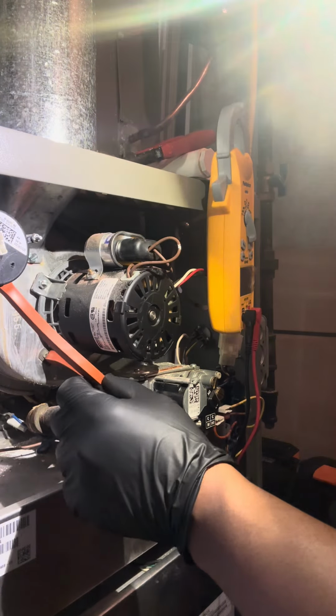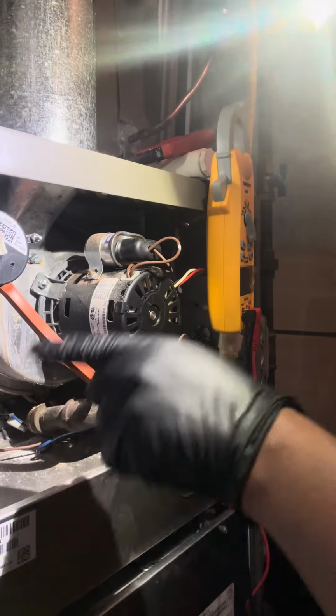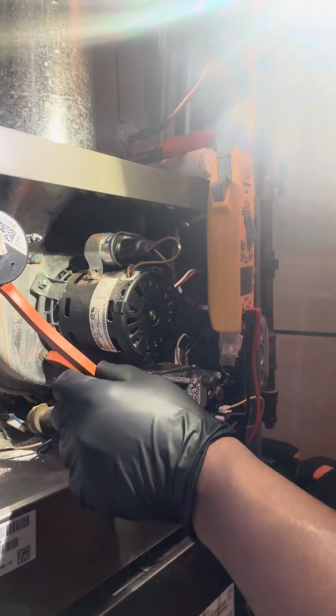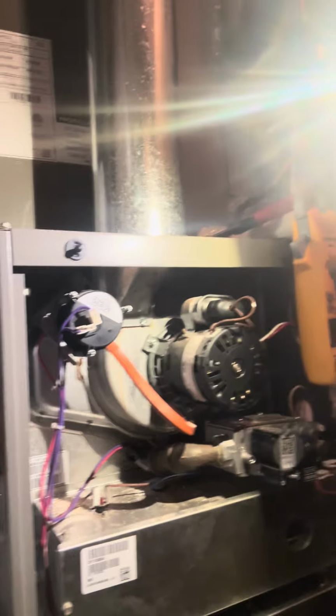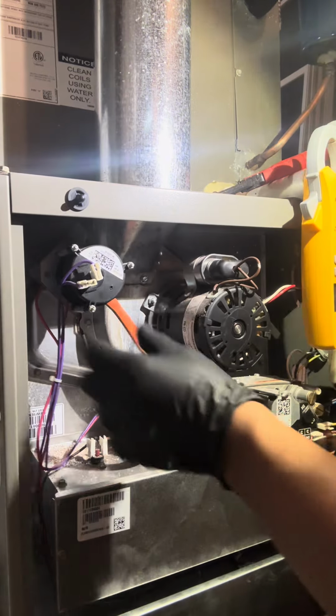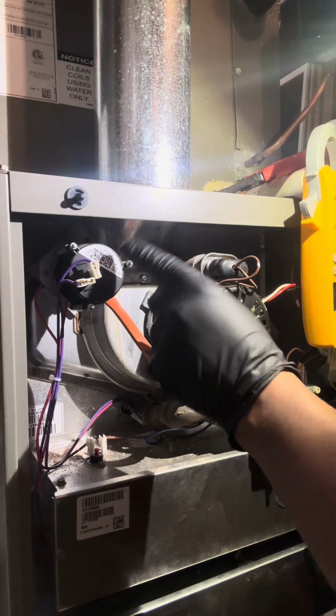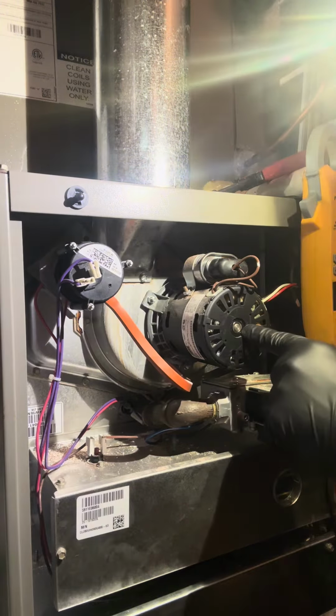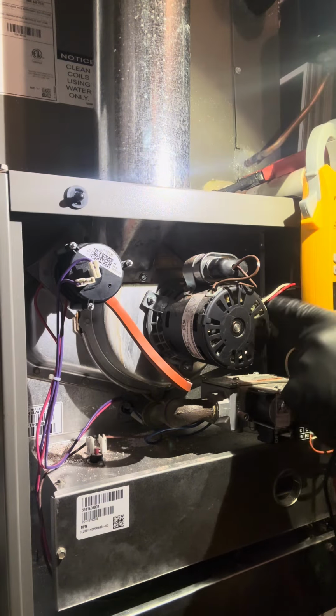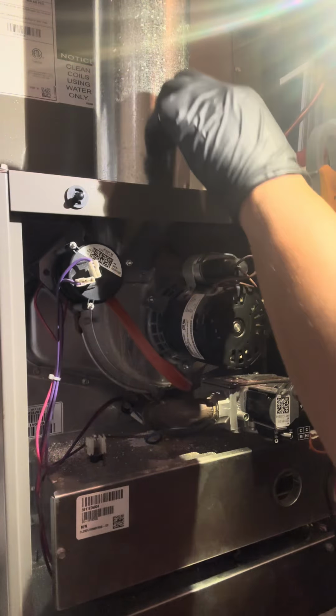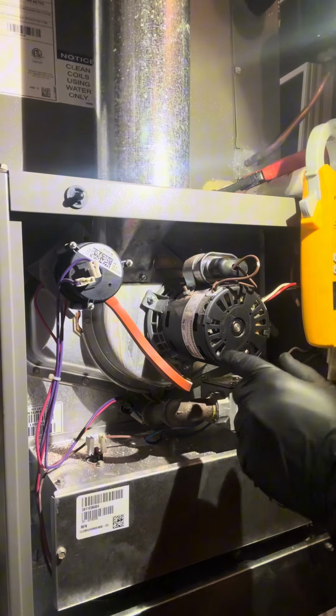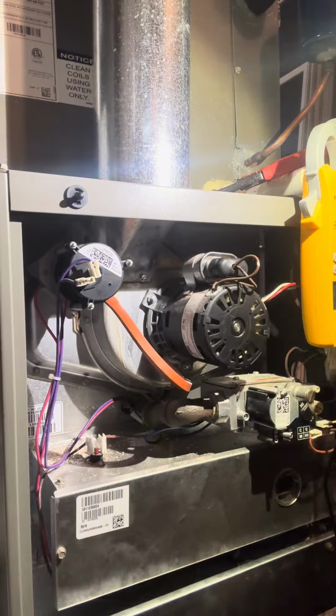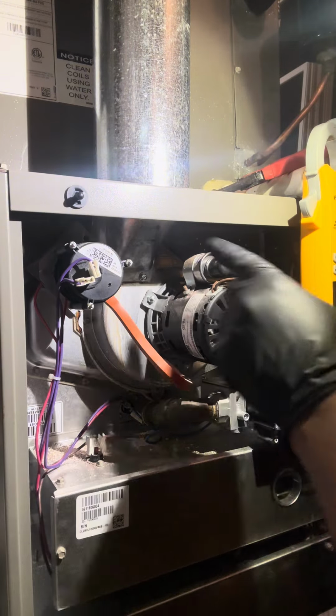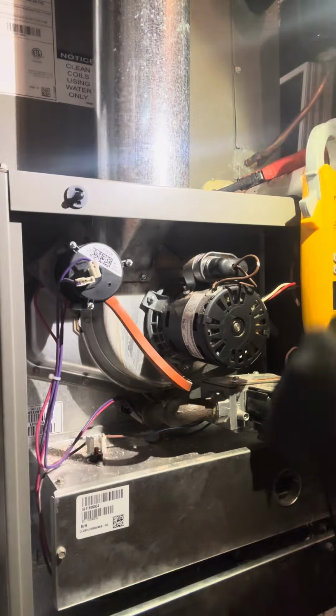On these SL 180s or 280s, most of the Lennox's 80% furnaces have this pressure tube right here. So let me make sure you guys can see. This is a pressure switch. The pressure switch is a safety. It is to prove that your inducer motor is indeed working. Because like I said, your inducer motor is pushing all of your toxic gases out of your house. And obviously, you need to have some safeties in place to make sure that your toxic gases are being pushed out of your home. That's where your pressure switch comes in.